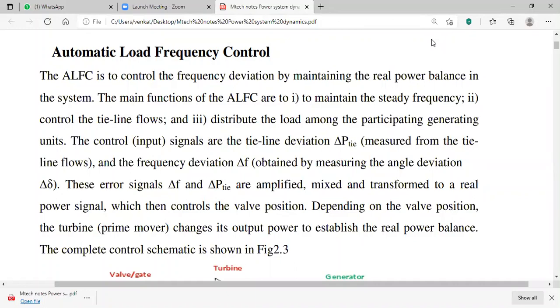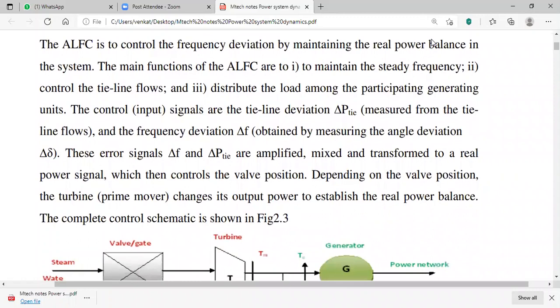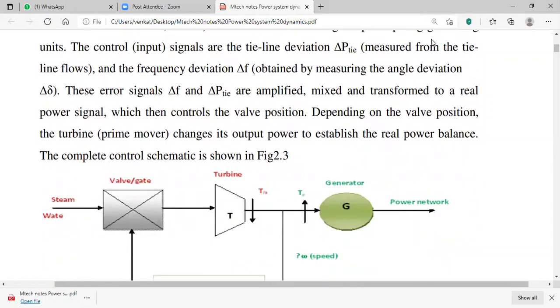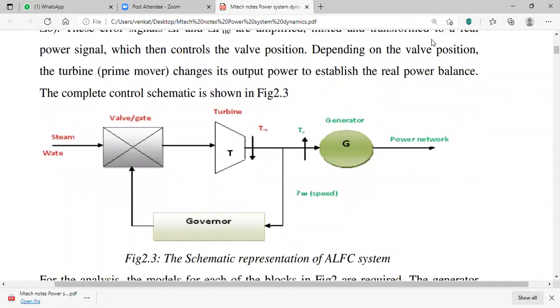The control input signals are tie line deviation delta P-tie, measured from tie line flows, and frequency deviation delta F obtained by measuring the angle deviation delta-delta. These errors — frequency deviation and tie line power — are amplified, mixed, and transformed to a real power signal which controls the valve position. Depending on valve position, the turbine changes its output power to establish a real power balance. You always need to monitor delta F and delta P-tie.